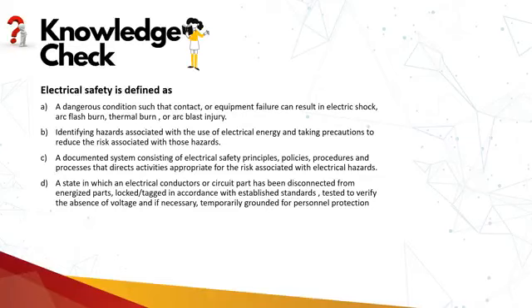I think in the last session we saw, in the arc flash boundary, it starts from 1.2 cal per centimeter square, and it's kind of a second degree burn. Yeah, basically 1.2 cals per centimeter square is the point from where 70E says that the arc flash hazard exists.